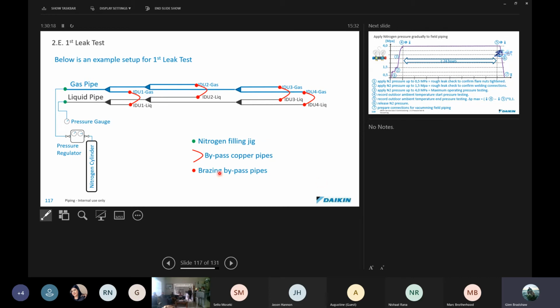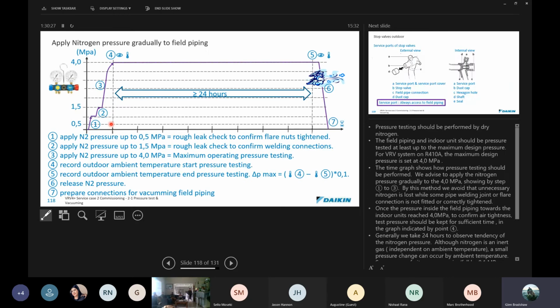And again, all of these pipes are brazed. Don't ever try to do a pressure test with hose clamps or anything like that. When you're doing pressure testing, you never ever take it straight to the maximum pressure first up. You always apply 0.5 megapascals.